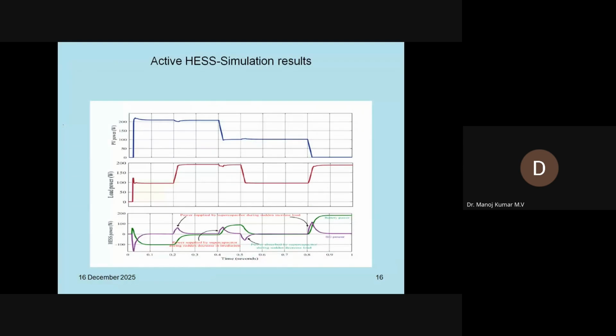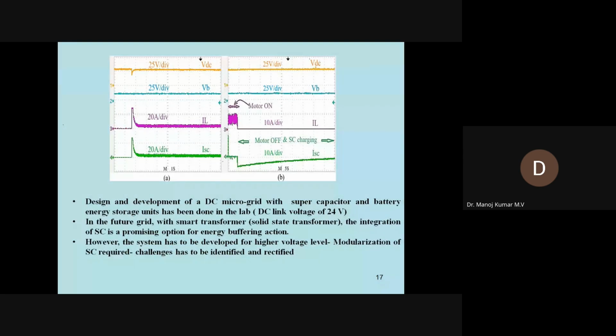This is implemented and working as per expectation - the supercapacitor supplies the transient current and the battery supplies the steady state current. The additional advantage of combining supercapacitor and battery storage is that it increases the life of the battery, because as the current stress or change of current is very less, the battery is able to withstand more and its life is improved.